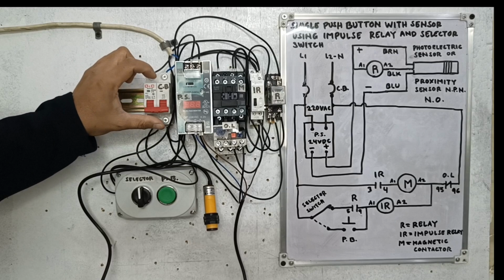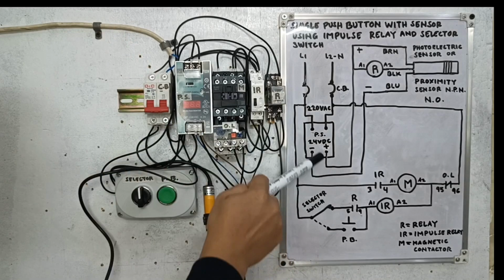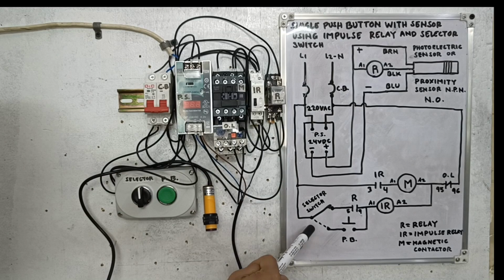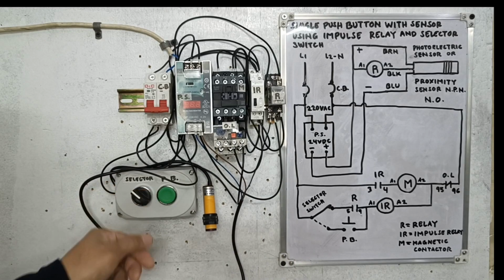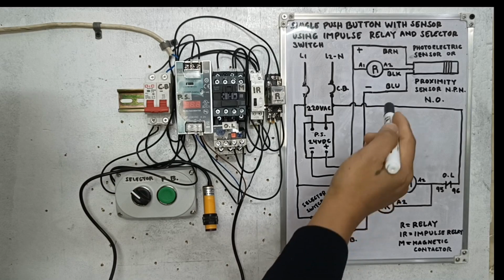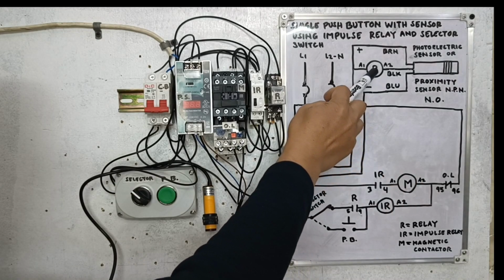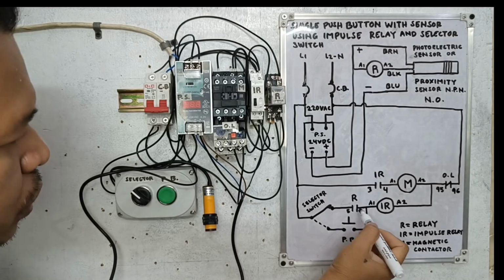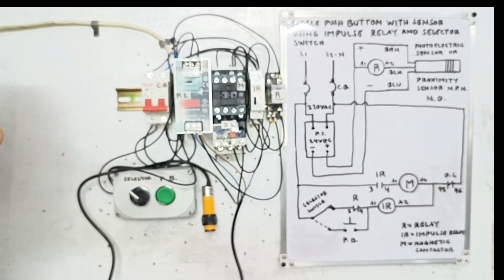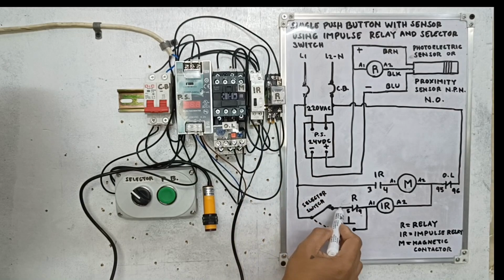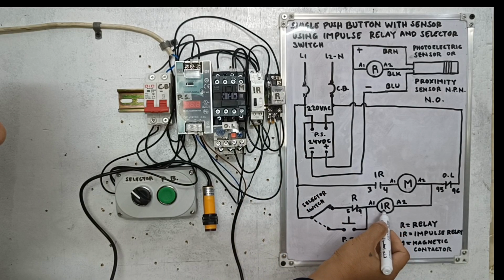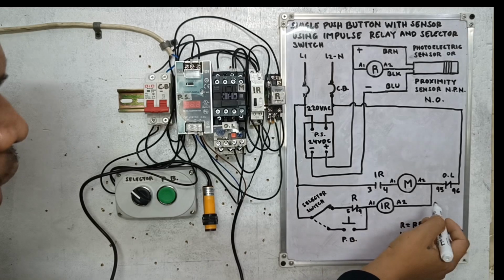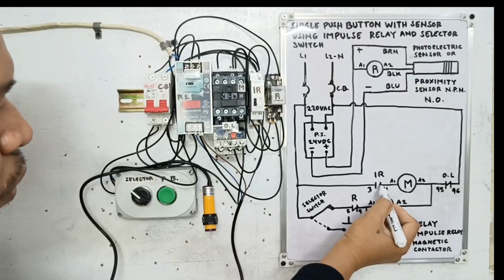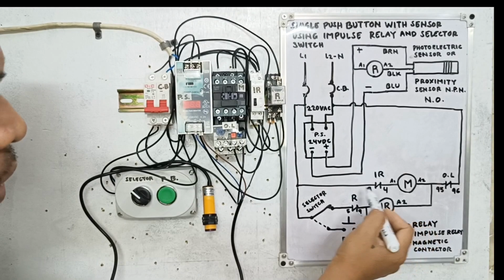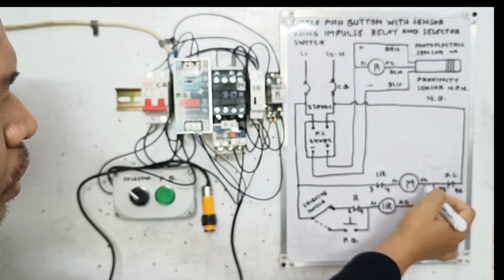If we turn on this circuit breaker, the power supply will activate. If the selector switch is like this, and the sensor can sense, the relay will activate and this contact will close. This contact will close. Now the current passes here and activates the impulse relay. After the impulse relay activates, this one also will close. And then the magnetic contactor also activates because there is a connection.